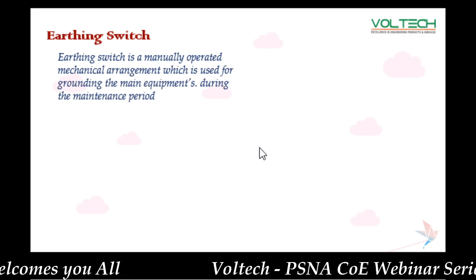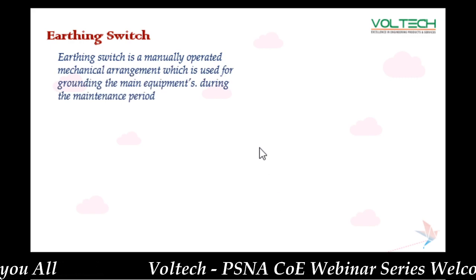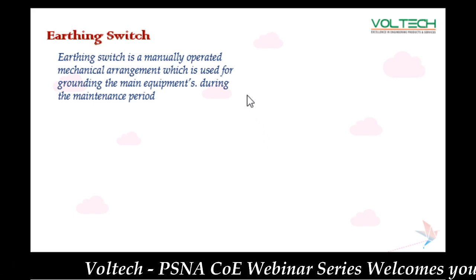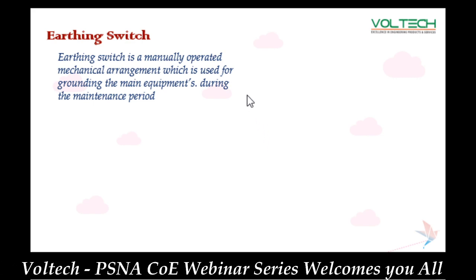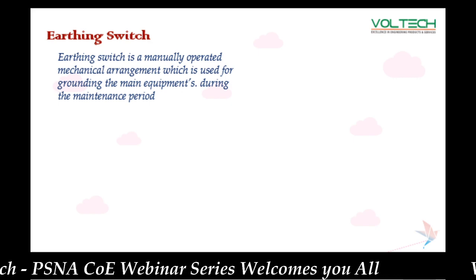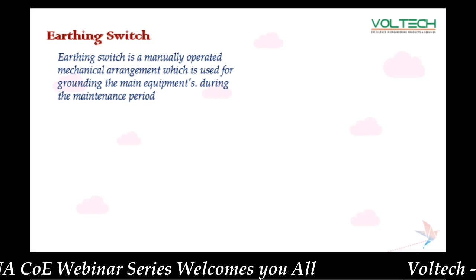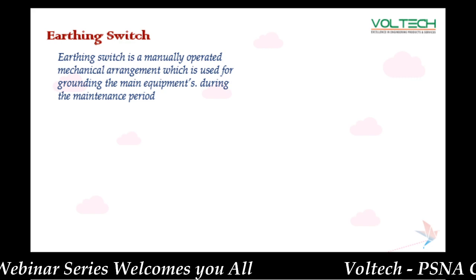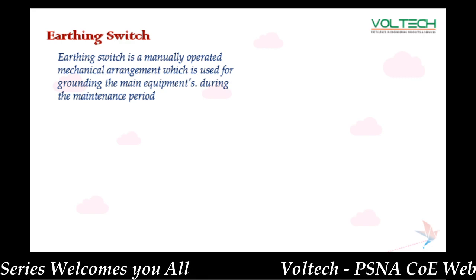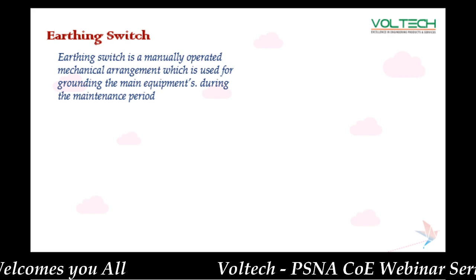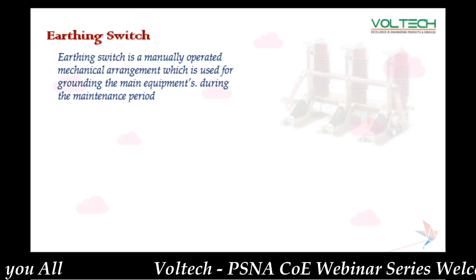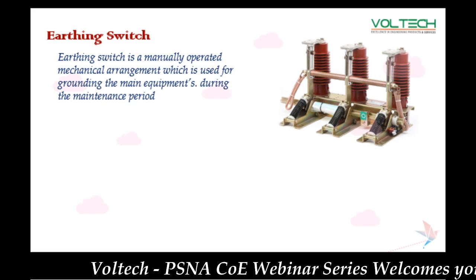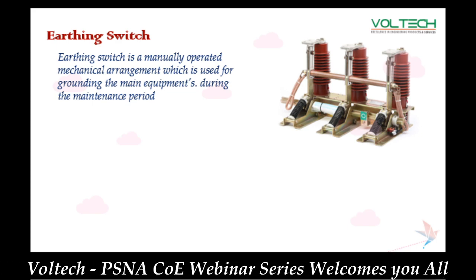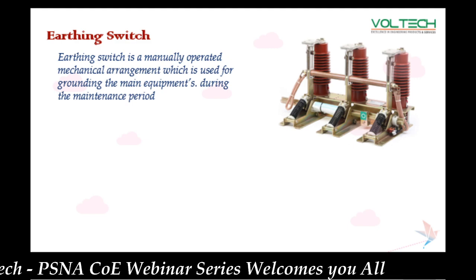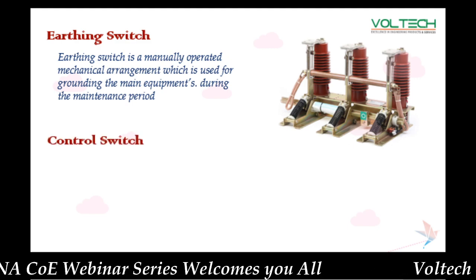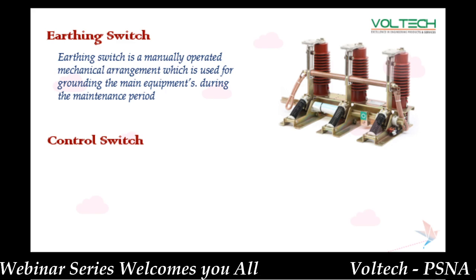Earthing switch. The earthing switch is a simple mechanical construction we made in the switchgear. At the bottom of the switchgear we connect the external circuit. That means the external circuit we should not interrupt with our busbar or any other breakers. If you want to take maintenance, you have to disconnect the external circuit and make earthing for safety. For that we are using this earthing switch. This earthing switch is mechanically operated. We can pull it manually to close or open the circuit. Sorry, earthing switch.